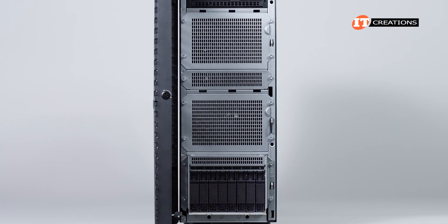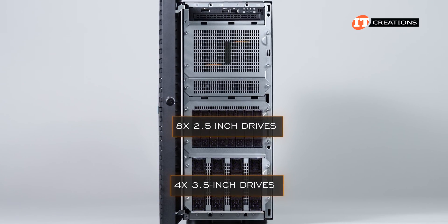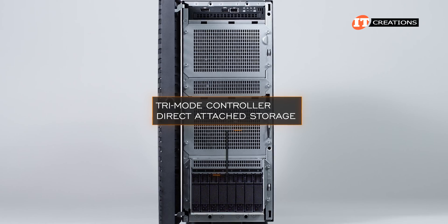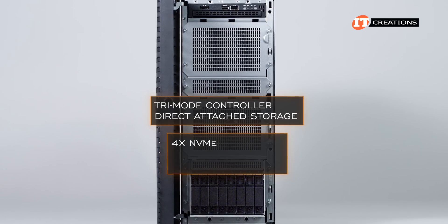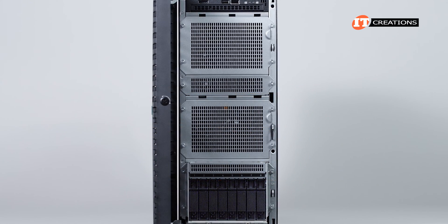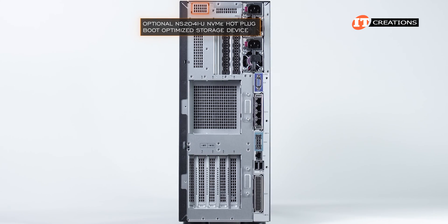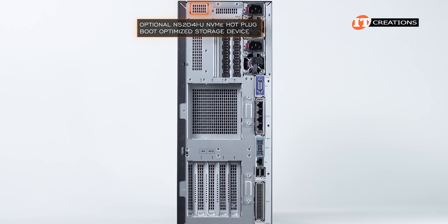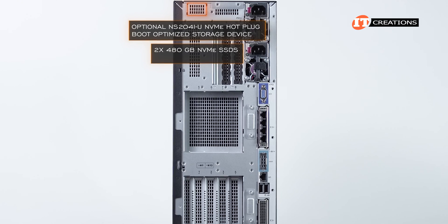The system also supports a mixed drive configuration using four LFF drive bays in Box 3 paired with eight SFF drive bays in Box 2, and eight more in Box 1. Outfitted with a tri-mode controller or using direct-attached storage enables up to four NVMe U.3 or four U.2 NVMe drives. System board connectors only allow for SATA drives. On the back at the very top of the chassis is a place for an optional NS204i-U NVMe hot plug boot optimized storage device — it has two 480GB NVMe SSDs and automatically creates a RAID 1 mirror volume for redundancy. It's totally plug-and-play and requires no setup.